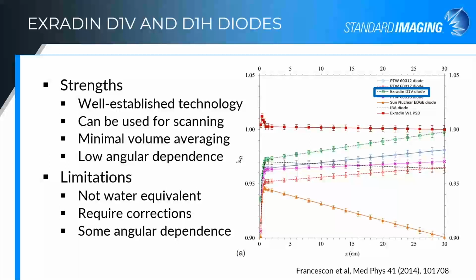Limitations of these diodes, not unique to our diodes, but limitations that should be known, is that the diodes are not water equivalent. So you do require corrections for the impact of the higher density diode compared to the water. And there is some angular dependence. They are not perfect. You can't just go shoot them from the side and expect it to be exactly equivalent to what you would get straight on. But they are great for scanning or for some of those phantom measurements.